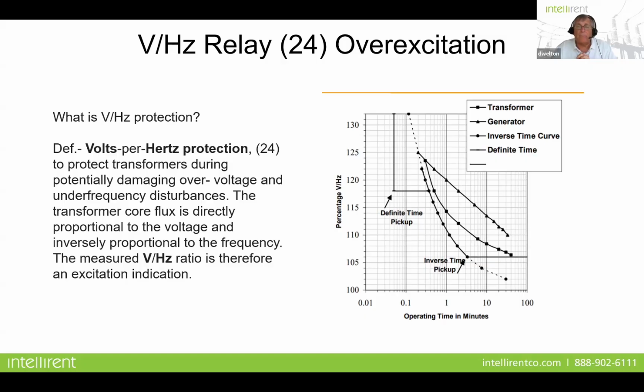So this is kind of what the protection curve looks like. It kind of looks like an overcurrent relay where you have your percentage of volts per hertz and your operating time in minutes. And you can see that you have one for the transformer, you have one for the generator, and then you have your actual relay setting that you're going to apply that will protect both generator and transformer. And one of the things that's important here is that NERC tells us that, yes, we must disconnect. We want to protect our equipment, but they also tell us we want you to stay online if it's just a transient that's not going to damage any equipment. And that's why these inverse time characteristics are applied. We don't want a definite time to say, oops, I'm over my volts per hertz rating, I've got to trip immediately. That's not how it's going to work.